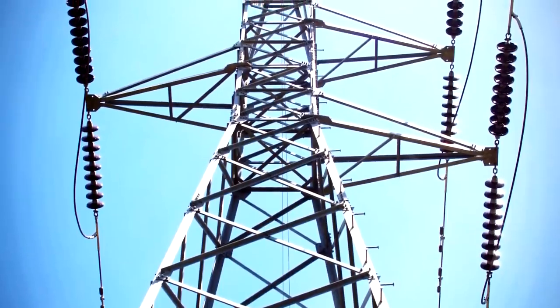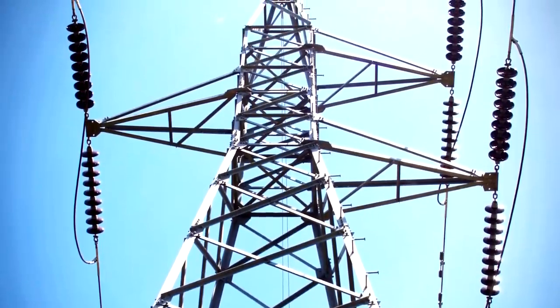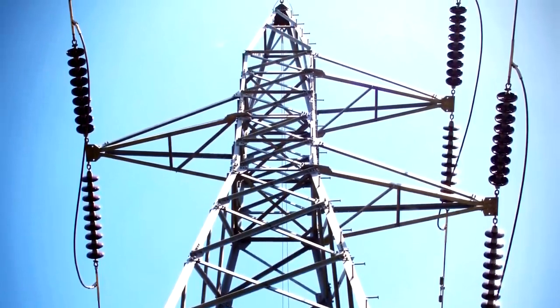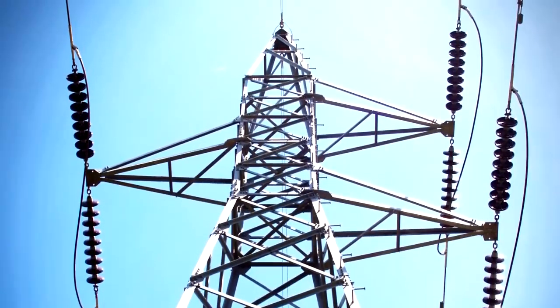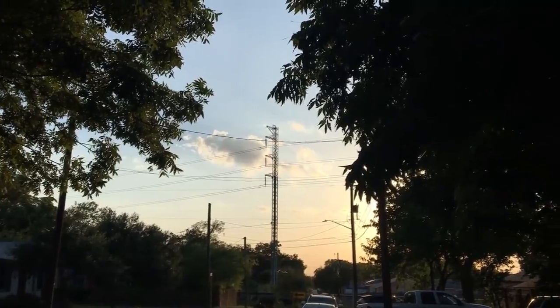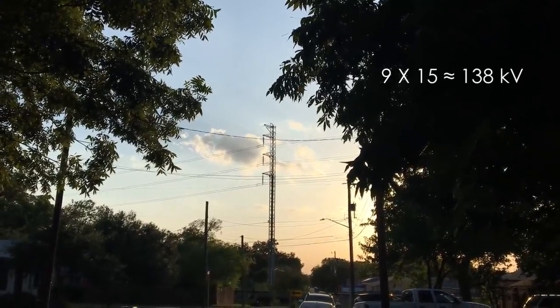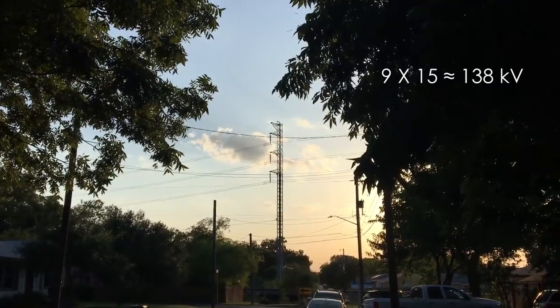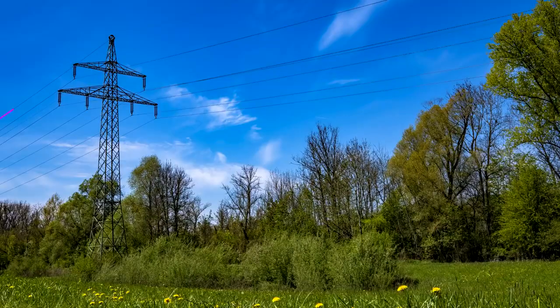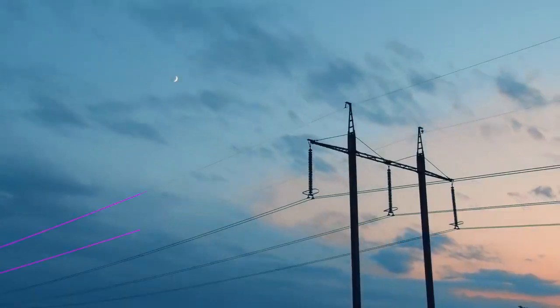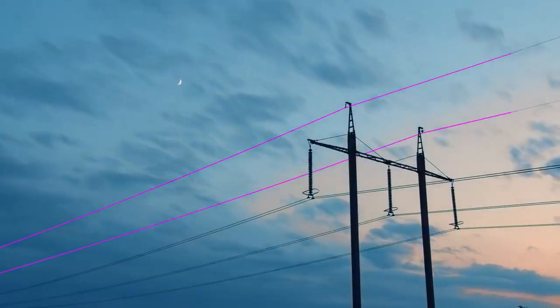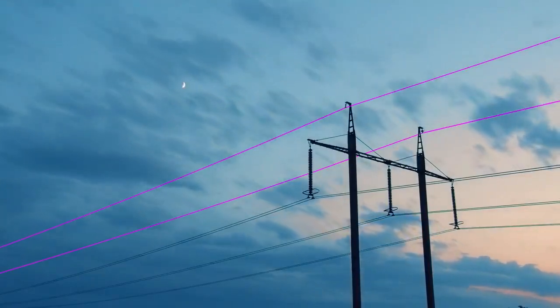These discs are somewhat standardized, so this is an easy way to get a rough guess of a transmission line's voltage. Just multiply the number of discs by 15. For example, this line near my house has 9 discs on each insulator, and I know it's a 138 kilovolt line. You'll also often see smaller conductors running along the top of transmission lines. These static or shield wires aren't carrying any current, they're there to protect the main conductors against lightning strikes.